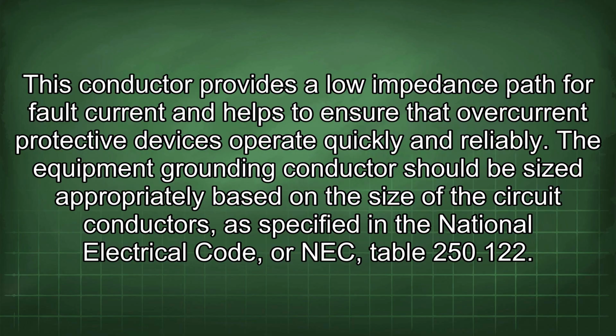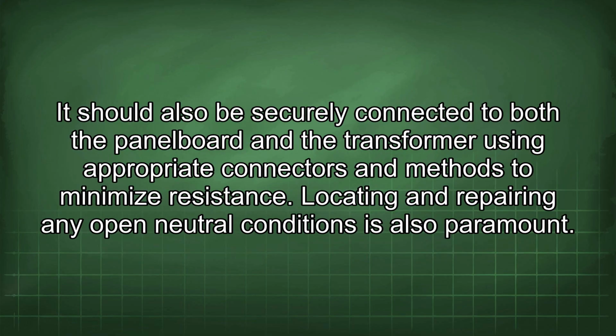This conductor provides a low impedance path for fault current and helps to ensure that overcurrent protective devices operate quickly and reliably. The equipment grounding conductor should be sized appropriately based on the size of the circuit conductors, as specified in the National Electrical Code, or NEC, Table 250.122. It should also be securely connected to both the panel board and the transformer using appropriate connectors and methods to minimize resistance. Locating and repairing any open neutral conditions is also paramount.